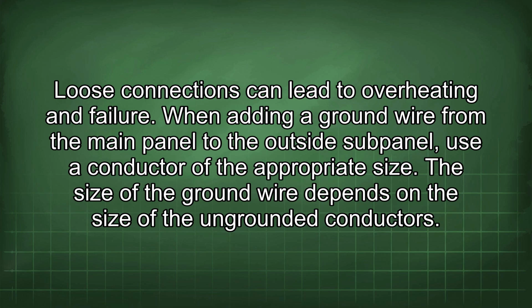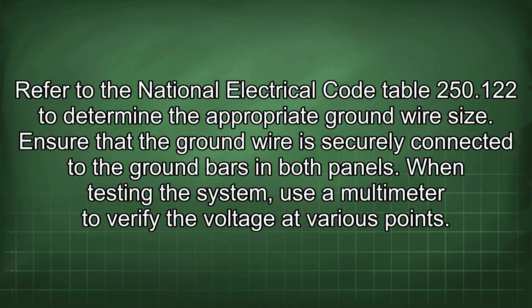When adding a ground wire from the main panel to the outside subpanel, use a conductor of the appropriate size. The size of the ground wire depends on the size of the ungrounded conductors. Refer to the National Electrical Code Table 250.122 to determine the appropriate ground wire size. Ensure that the ground wire is securely connected to the ground bars in both panels.